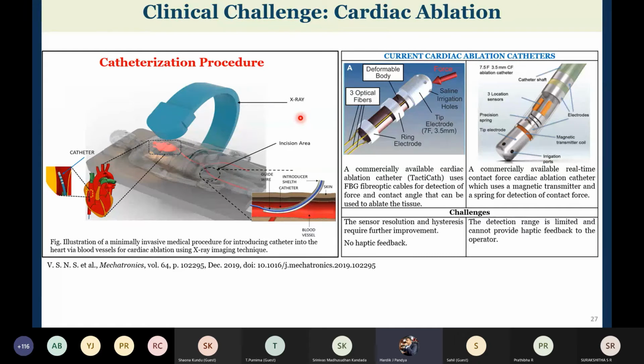So measuring the contact force when the catheter is inserted in the heart is a very important problem. More importantly, there is no haptic feedback to these catheters. So we were thinking, and we now have designed, or I should say we are designing, a catheter using an advanced force sensor to understand the catheter contact force. I'll show you in a few slides. The one you can see here is based on optical fibers, and it's a commercially available catheter without haptics. It's called TactiCath. What you have seen here is another commercial catheter called the Thermocool ablation catheter from Biosense Webster, California.